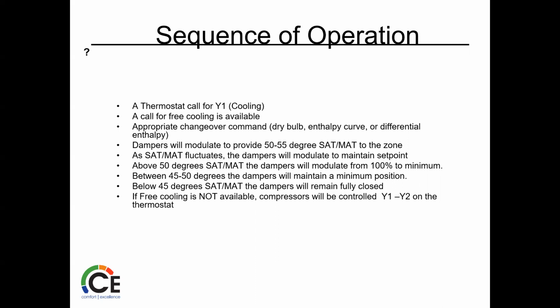Dampers will modulate to provide 50 to 55 degree supply air or mixed air temperature to the zone. As supply air temperature or mixed air temperature fluctuates, the dampers will modulate to maintain a set point. Above 50 degrees, those thermistors, the dampers will modulate from 100% to minimum. Between 45 and 50 degrees, the dampers will maintain a minimum position. Below 45, the dampers will remain closed. All right, important thing there. Test question: below 45 degrees, SAT, MAT, the dampers will remain fully closed. Free cooling is not available. Then, of course, compressors are controlled by Y1, Y2, and the thermostat.